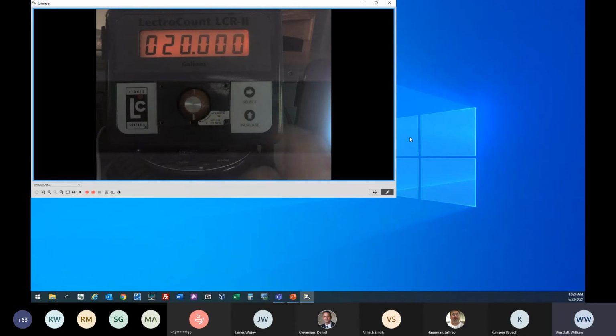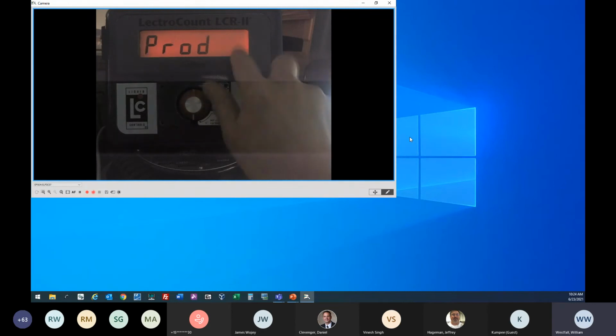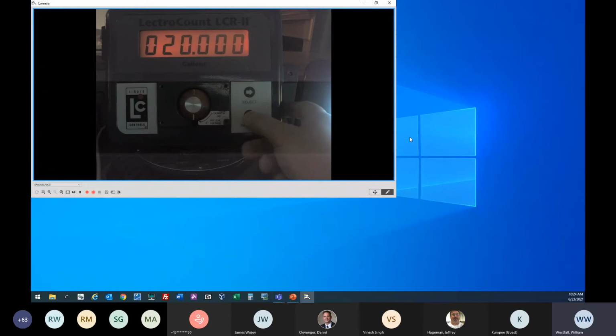So in order to start a calibration delivery, once you know that you're in the right product, no flow rate, there's your temperature, all you have to do is hit the increase key. You'll get a counter test, and then you'll go ahead and start filling up your prover. Once you are done with your prover, let's say it gets filled up, let's say it's a 25-gallon prover here, you hit increase one more time to stop your delivery.